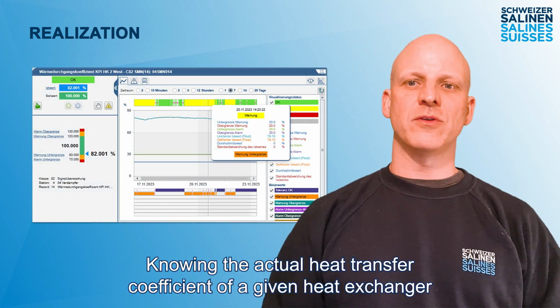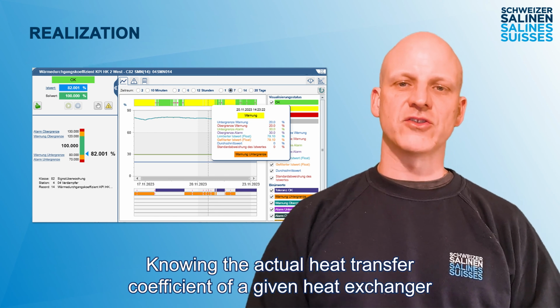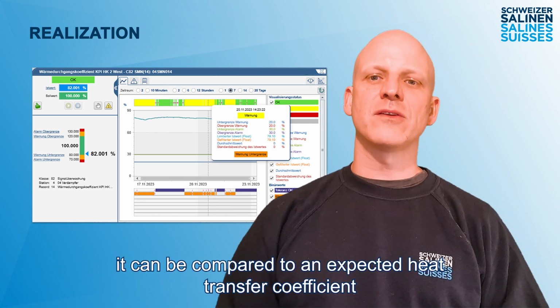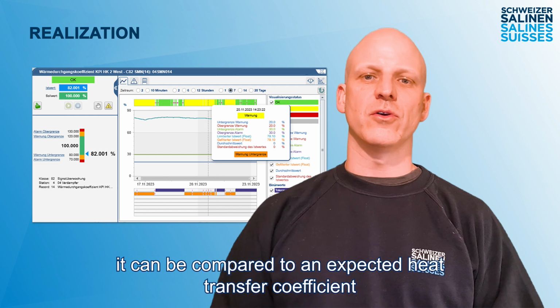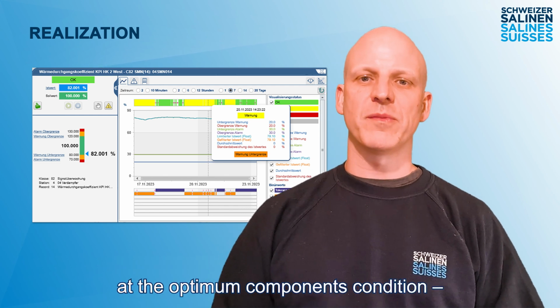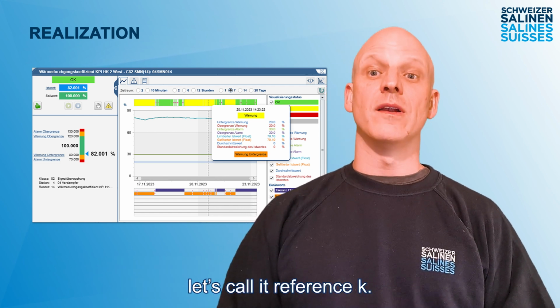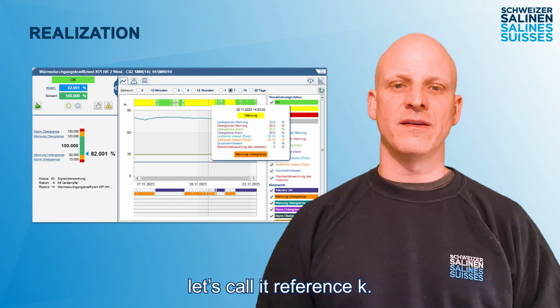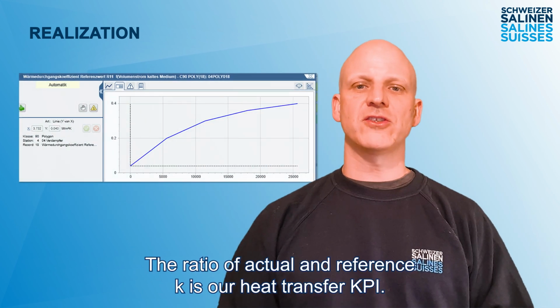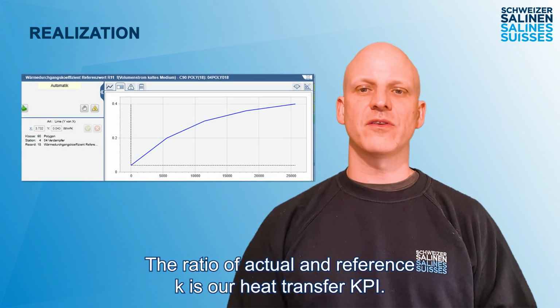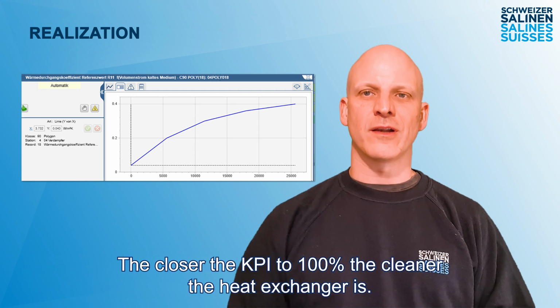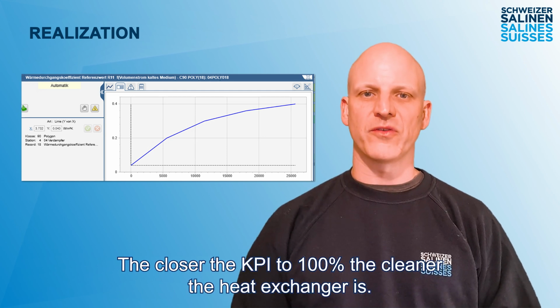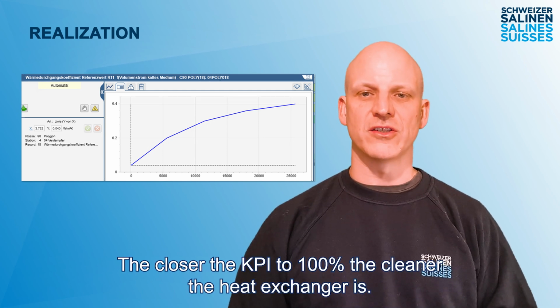Knowing the actual heat transfer coefficient of a given heat exchanger, it can be compared to an expected heat transfer coefficient at the optimum operating condition. Let's call it reference K. The ratio of actual and reference K is our heat transfer KPI. The closer the KPI is to 100%, the cleaner the heat exchanger is.